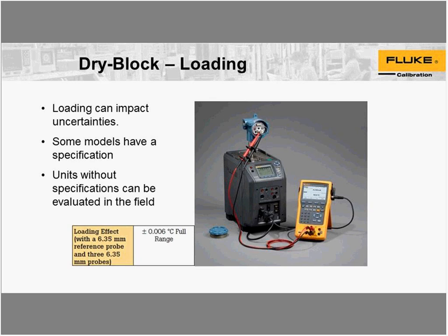So again, really small on the loading, but it is a consideration, especially if you're doing large quantities of units or the physical size of the actual sensor is large. The temperature range is also something that can play in, especially if you're going to the extreme hot or cold with a fairly large size unit under test. So again, that loading effect spec that we're providing is just to give you an idea of what to expect potentially when running the unit.